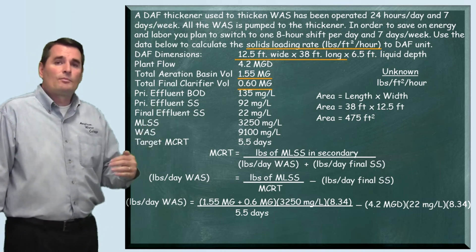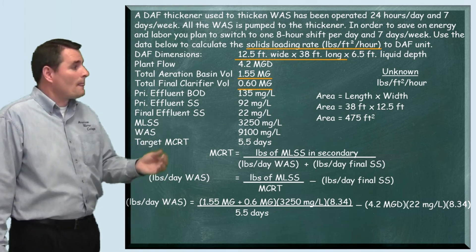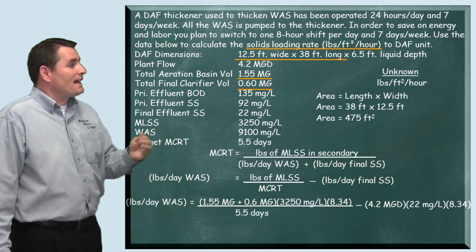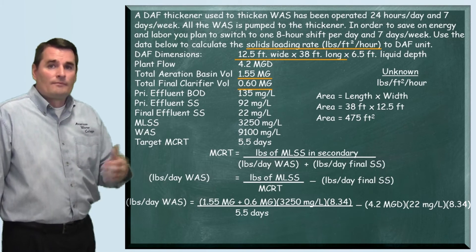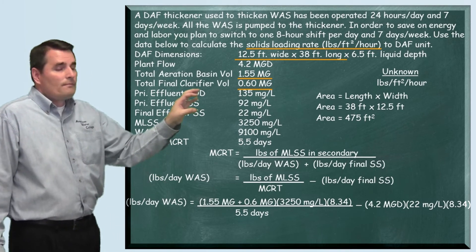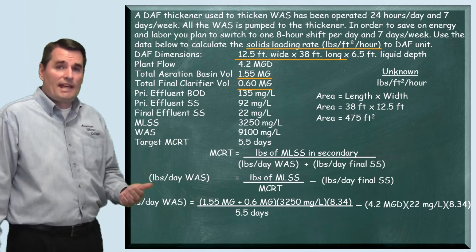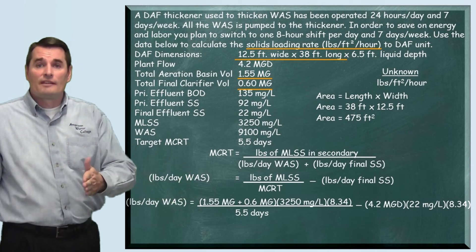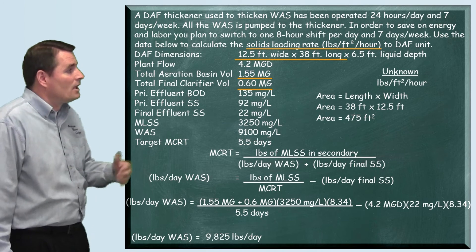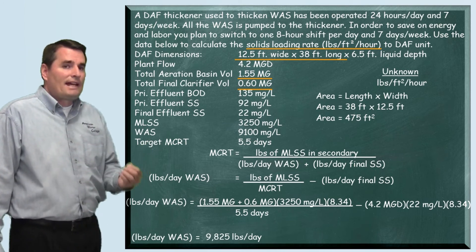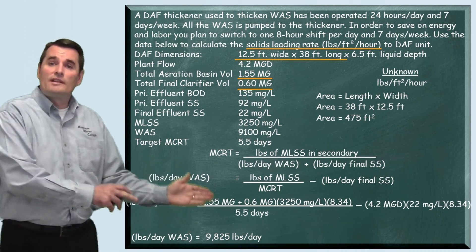Then we subtract out the pounds per day leaving over the final weir, using the plant flow of 4.2 MGD times the effluent suspended solids concentration of 22 mg/L times 8.34. Once we do this math and calculate it out, we get 9,825 pounds per day of waste activated sludge going to the thickener — because the problem told us all of the waste activated sludge is going to the thickener.